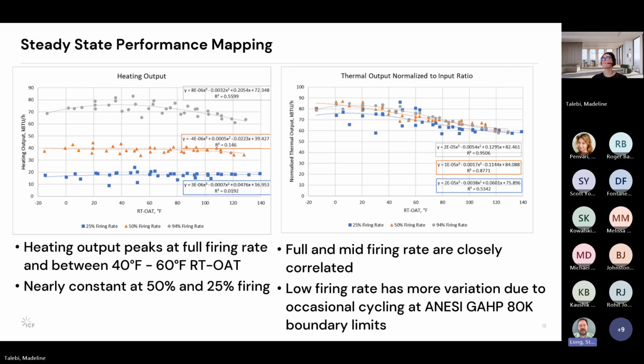In the field, part of the challenge is you're not only dealing with the unit itself, but you're dealing with the balance of the system. In the balance of the system, you may have a boiler that's cycling on and off because it's oversized, which we found to be the norm. And that brings down the overall efficiency. But if they pair it with a condensing boiler or a condensing instantaneous water heater, what you're finding is that the incremental gain of the GAHP isn't as much as you might otherwise expect, just because that one's topping it off at, say, 95% AFUE or the equivalent. So I'm going to say you're probably up to about 30% on the better cases and maybe 10% on lesser cases.